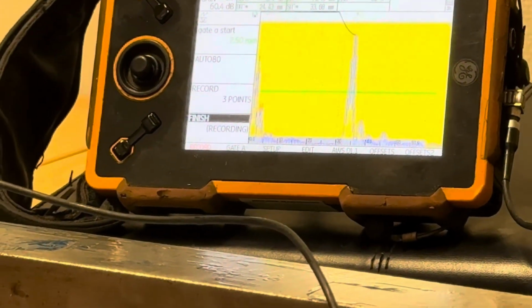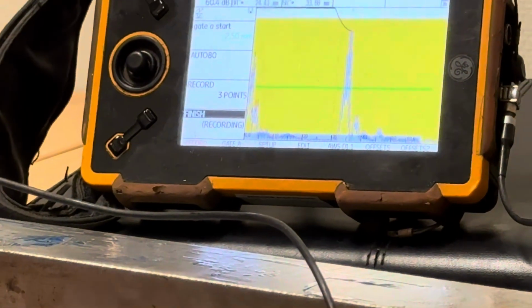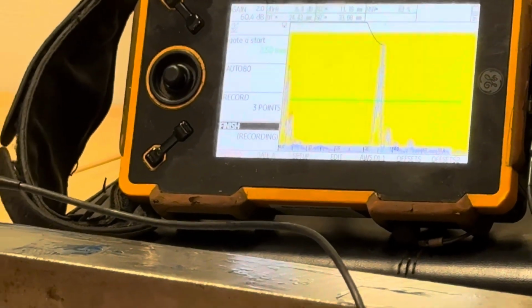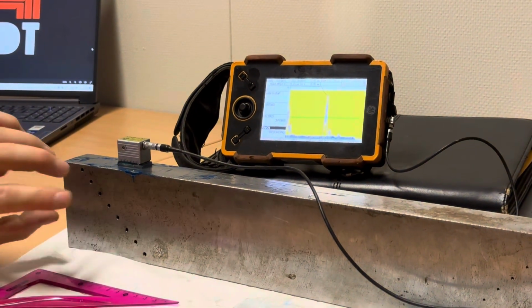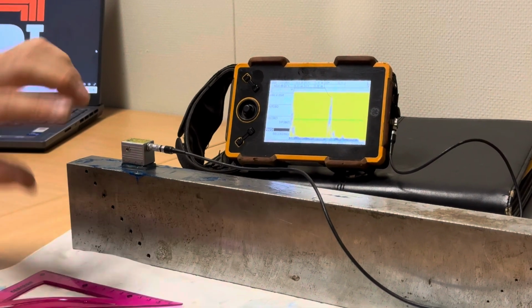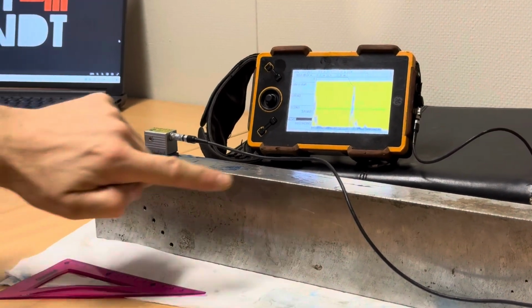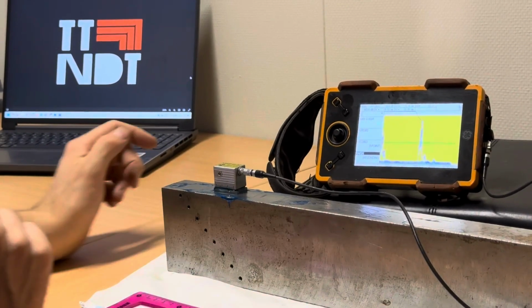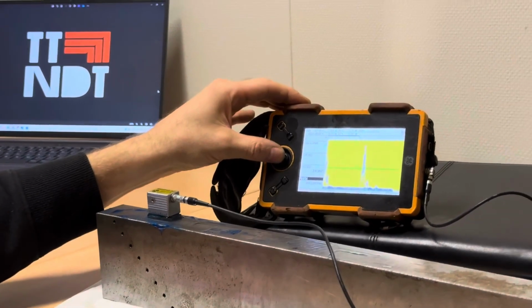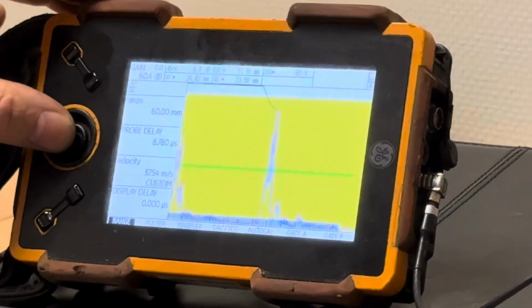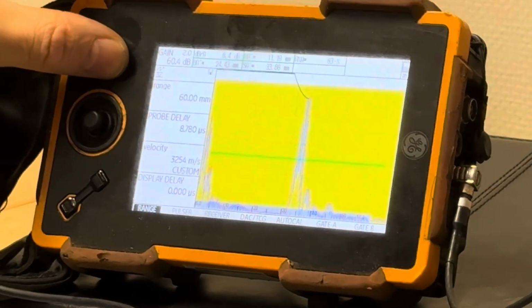If the distance is sufficient for us, then we finish and it's recorded. If this depth is not enough for us, then we look at the reflected signals. We can flip the calibration block to the other side and try to hit the points there. When we're done, we press finish and we get a result. We look at how it appears.